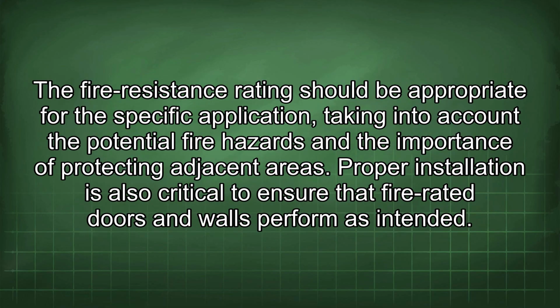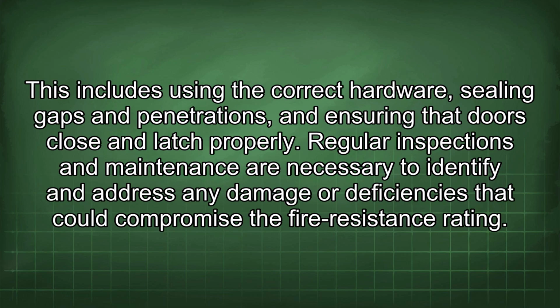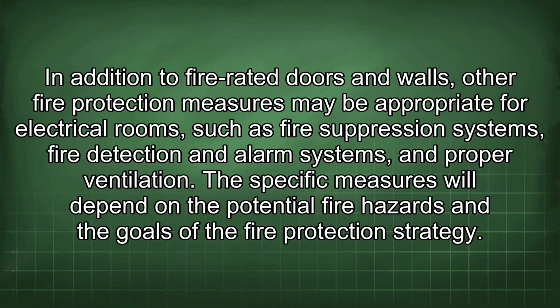The fire resistance rating should be appropriate for the specific application, taking into account the potential fire hazards and the importance of protecting adjacent areas. Proper installation is also critical to ensure that fire-rated doors and walls perform as intended. This includes using the correct hardware, sealing gaps and penetrations, and ensuring that doors close and latch properly. Regular inspections and maintenance are necessary to identify and address any damage or deficiencies that could compromise the fire resistance rating. In addition to fire-rated doors and walls, other fire protection measures may be appropriate for electrical rooms, such as fire suppression systems, fire detection and alarm systems, and proper ventilation.